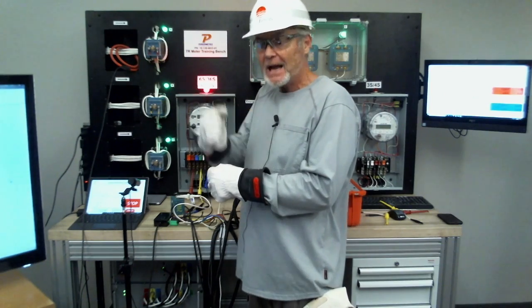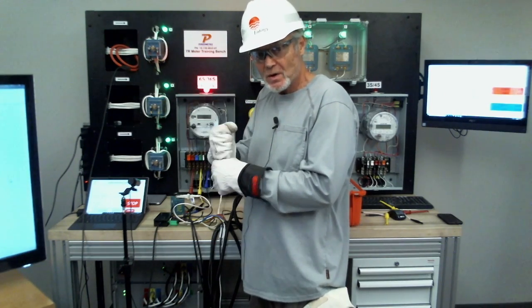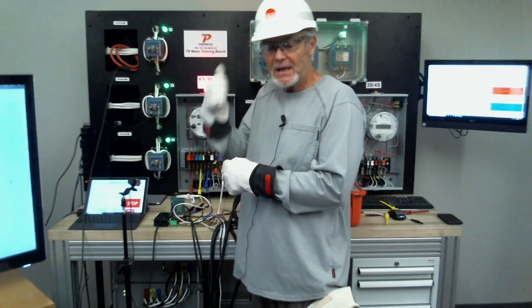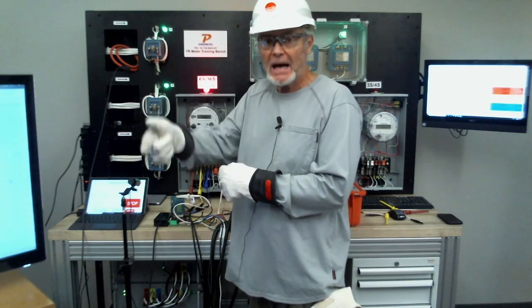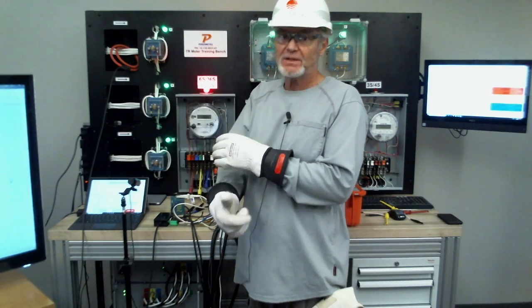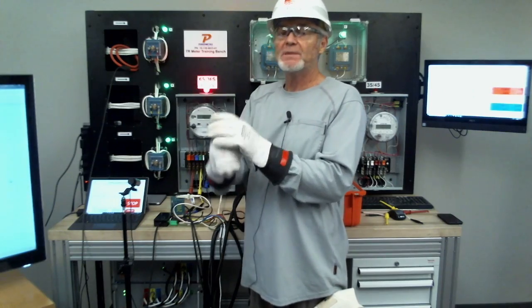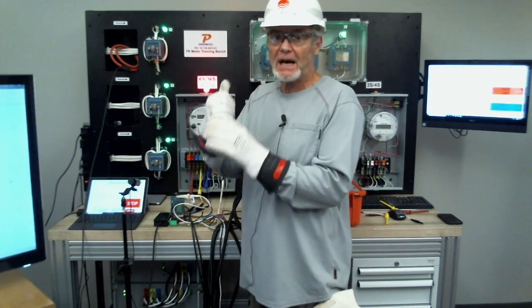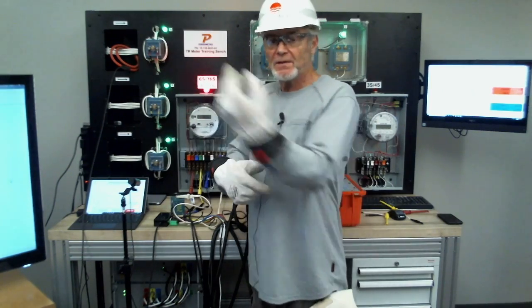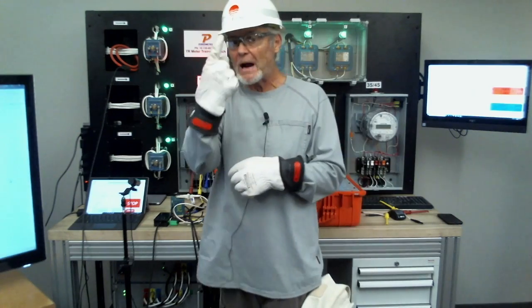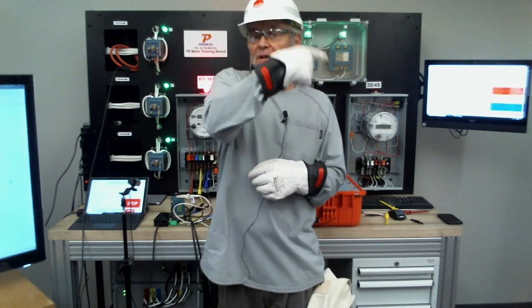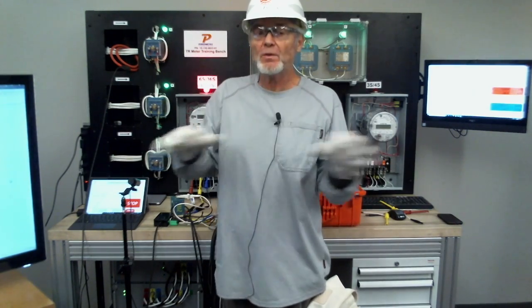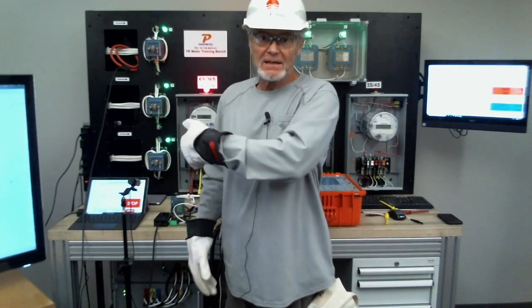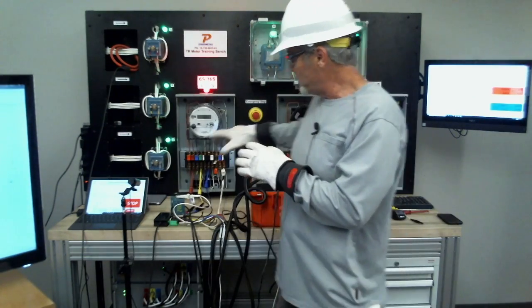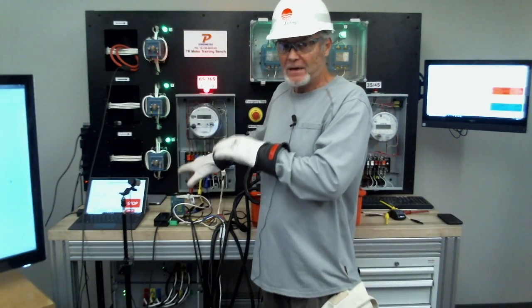on either end. And I always want to make sure that the drive end of that cable is sticking out of the dot side of that CT because it's coming in on the drive. So when it comes in on that drive, it needs to come into the dot side. So I don't care which way you feed it through the CT, just end up with the drive end hanging out of the dot side of the CT and you'll be right, okay, because it's going to come in that dot side.